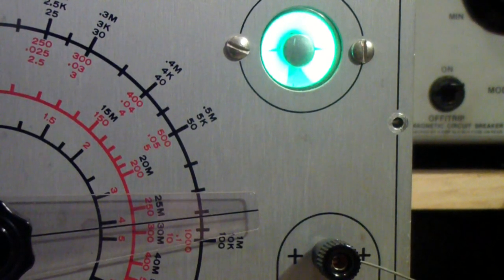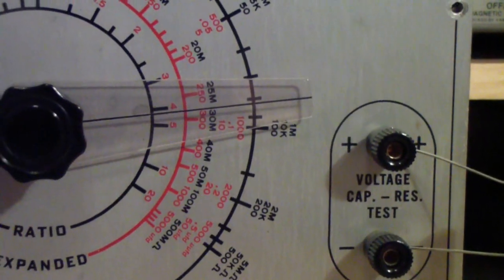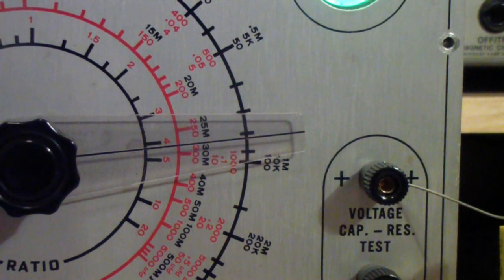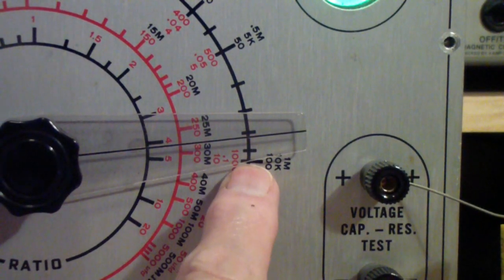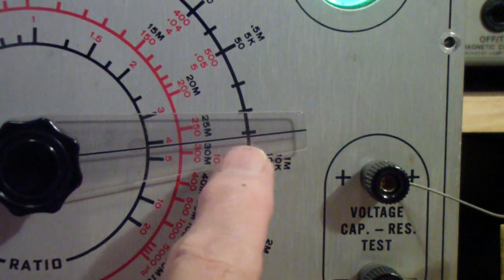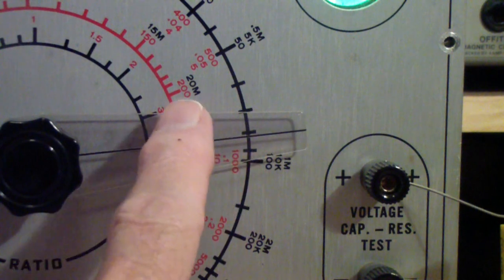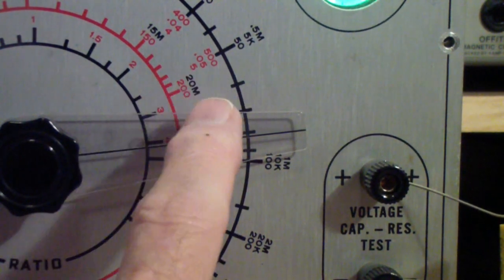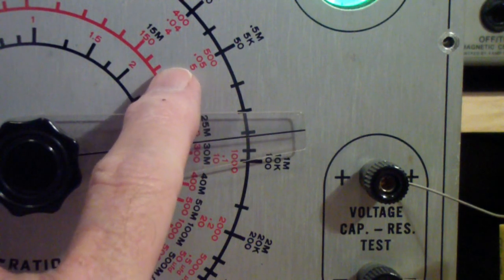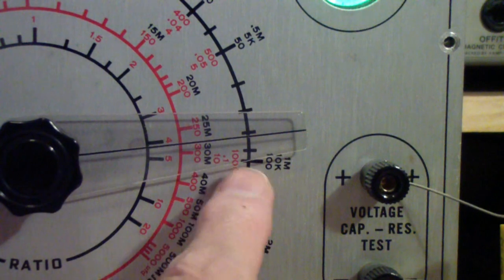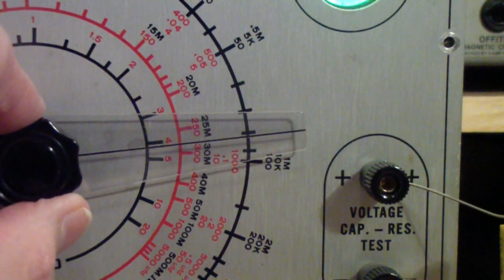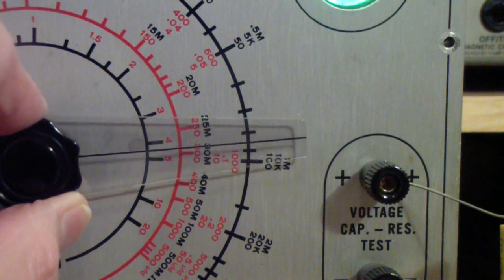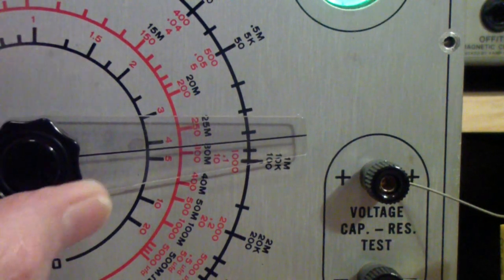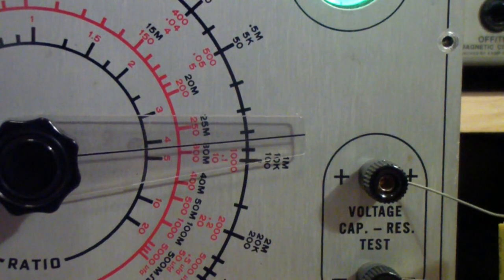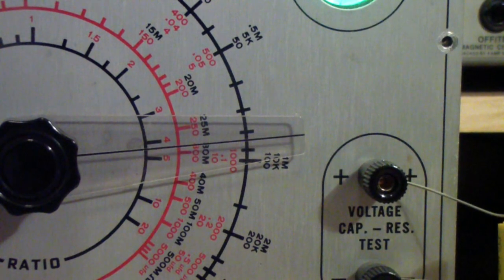You may or may not be able to see the reading at that point. It's just above 0.1, which is where it should be, right at 0.1 microfarad. This one is showing just a little less than 0.1. Let's see where it exactly balances, or is at maximum open. It's right there. So this particular capacitor is reading just slightly under 0.1 microfarad, but more than 0.09.